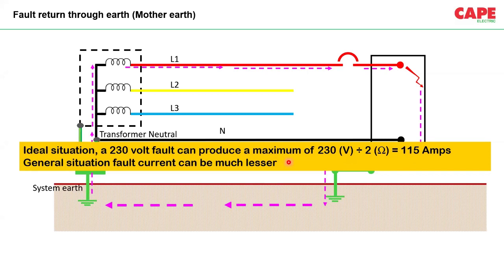Also, please note that fault means something which is happening to earth. Between line to line or between line to neutral, what is happening is a short circuit. So you should understand the difference between short circuit and a fault. What we are talking about is a fault. In a general situation, in a 230 volt TT network, fault current will be much lesser.